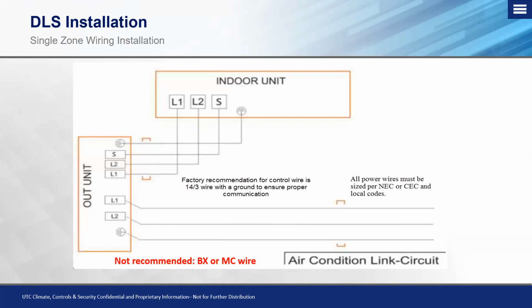So you can see in this application, we have our main power coming from our disconnect, which feeds into the outdoor unit. We have our L1, L2, and S terminals that feed from that outdoor unit bus bar to our indoor unit bus bar on the L1, L2, and S terminals. The factory recommendation for the control wire is 14-3 stranded wire with a ground to ensure proper communication. Okay. Of course, we don't recommend the BX or the MC style wiring, just because we're carrying high voltage and communication typically all in one jacket.